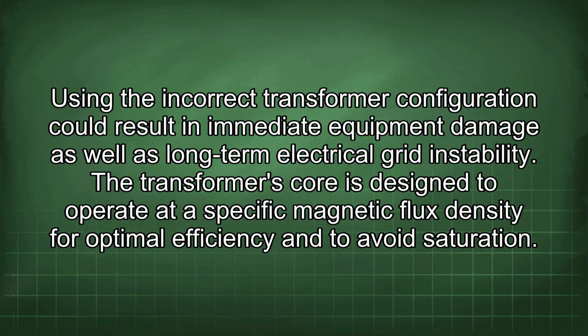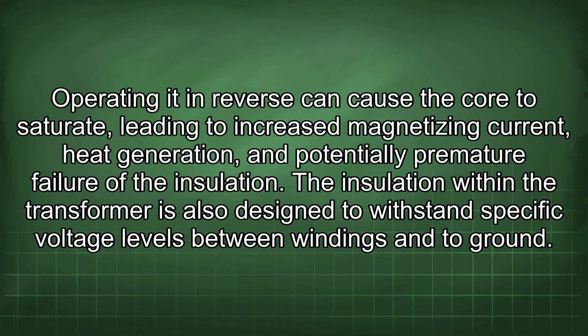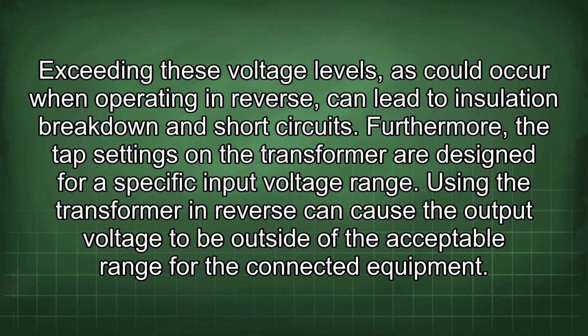The transformer's core is designed to operate at a specific magnetic flux density for optimal efficiency and to avoid saturation. Operating it in reverse can cause the core to saturate, leading to increased magnetizing current, heat generation, and potentially premature failure of the insulation. The insulation within the transformer is also designed to withstand specific voltage levels between windings and to ground. Exceeding these voltage levels, as could occur when operating in reverse, can lead to insulation breakdown and short circuits. Furthermore, the tap settings on the transformer are designed for a specific input voltage range. Using the transformer in reverse can cause the output voltage to be outside of the acceptable range for the connected equipment.